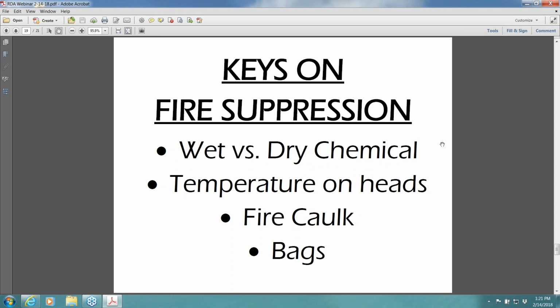If that's the case, you go to dry chem. Or if there aren't any sprinklers in the building, then you'd go to dry chemical, because you wouldn't want to sprinkle the whole building just to sprinkle the paint booth. A dry chemical system is basically a fire extinguisher with a bunch of pipes running out of it that go into heads in the booth. There's some sort of link that detects that a fire has happened, then trips and discharges the chemical agent into the booth.